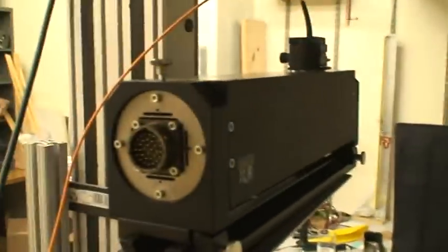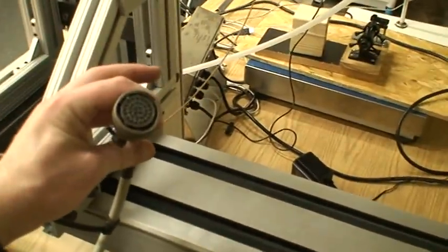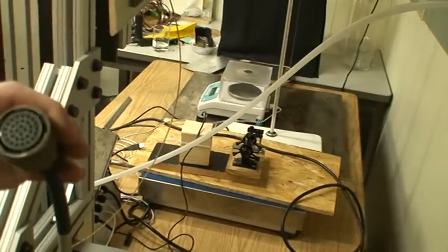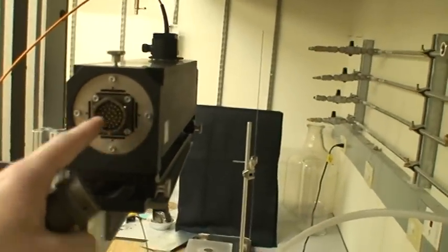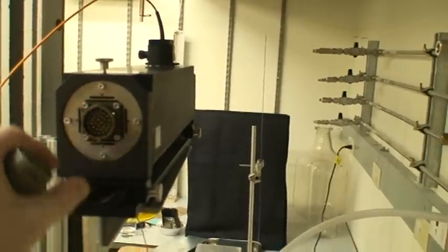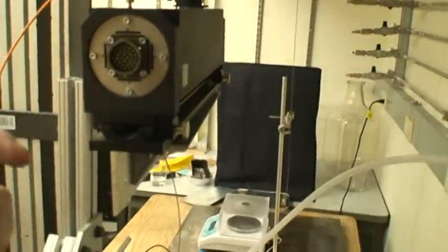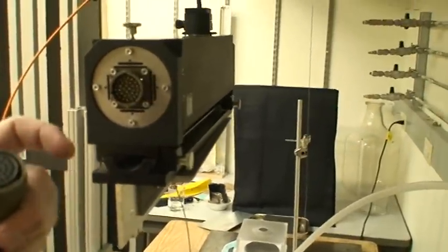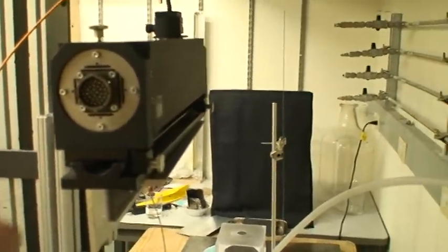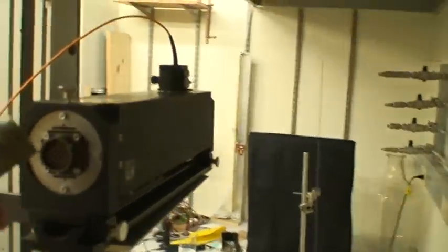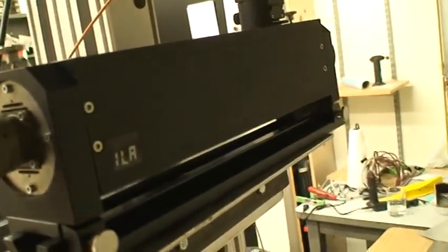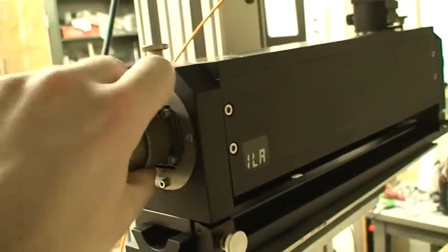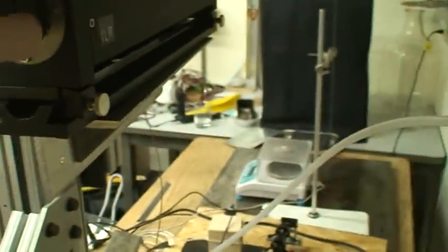This is the power and control cable, and you can see it goes here and there's a big notch. You can see there's a big tab here and a big notch here, so you know it's easy to tell this can only go on in one direction. Once you stick it on, you're going to rotate this top and it'll pull the unit into place. We stick it in, get this lined up, and then rotate this top bit, and you'll hear it click into place. So now it's attached.